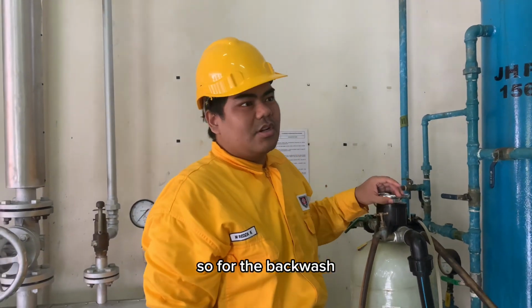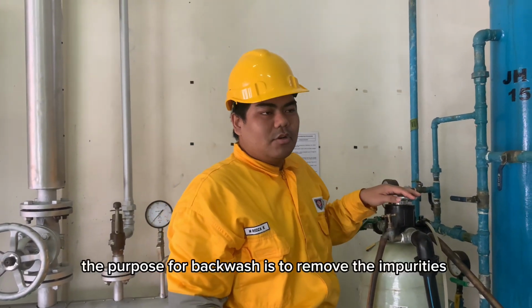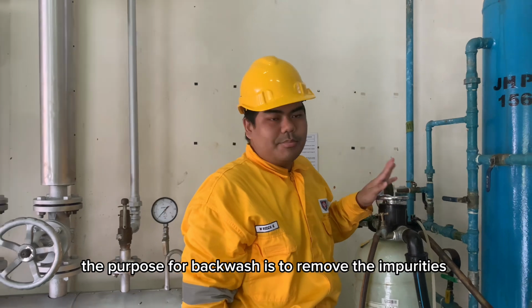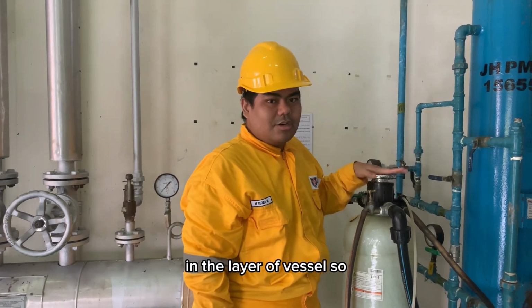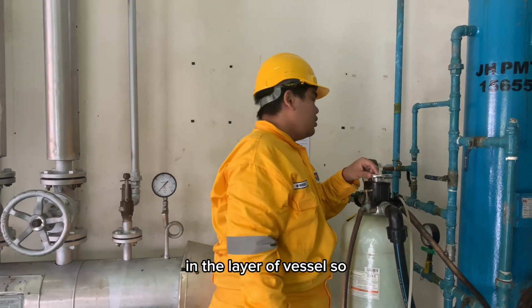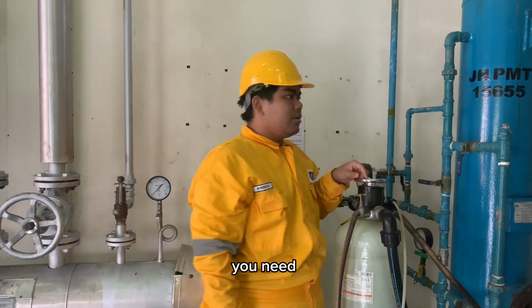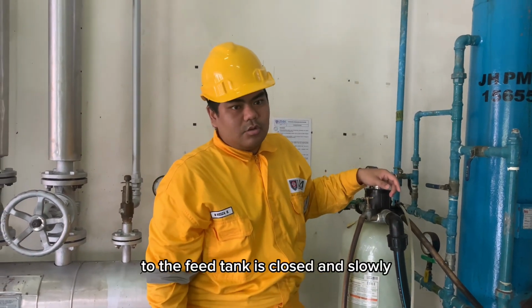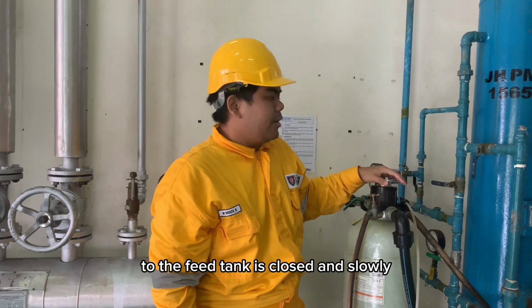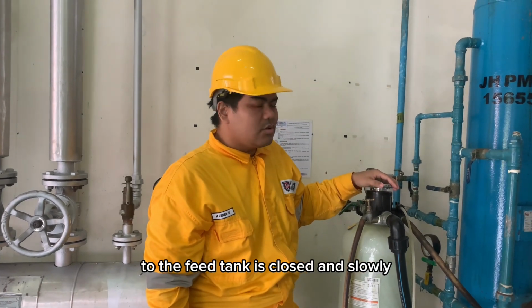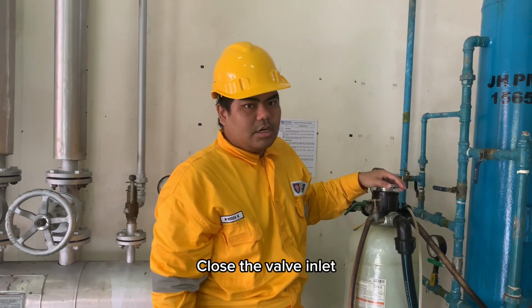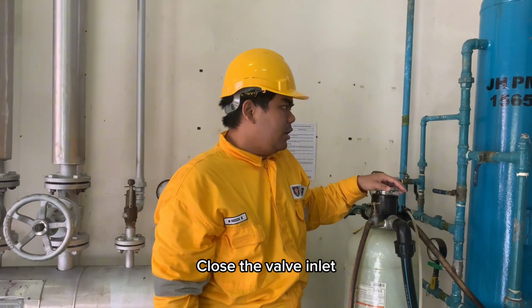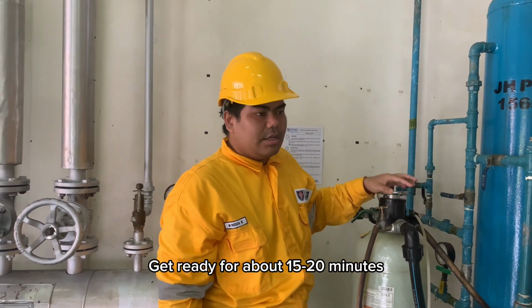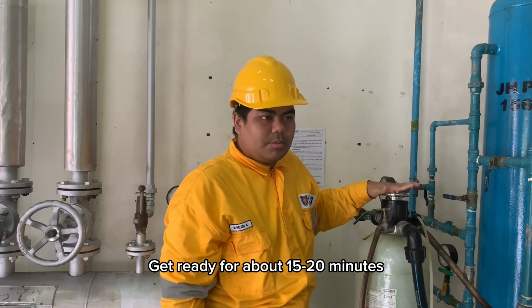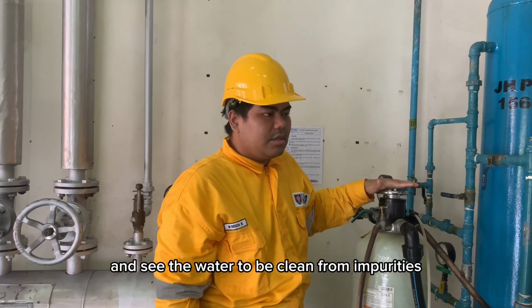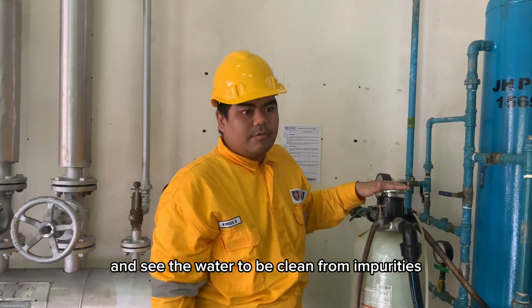So for the backwash, the purpose of the backwash is to remove the impurities in the layer of resin. You need to make sure the valve to the feed tank is closed, and after that slowly close the valve inlet. Then let it be for about 15 to 20 minutes, and see the water will be clean from the impurities.